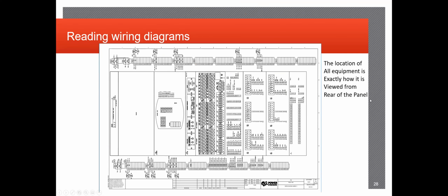For the wiring diagrams, this is a great print for troubleshooting purposes. It's extremely useful for identifying stuff that may differentiate. Usually the electricians will be working off of these primarily when they're putting in new equipment, new cable, new wiring, whatever. And our job is to work off of the DC schematics, because those functionally represent the protection scheme and the design intent properly.